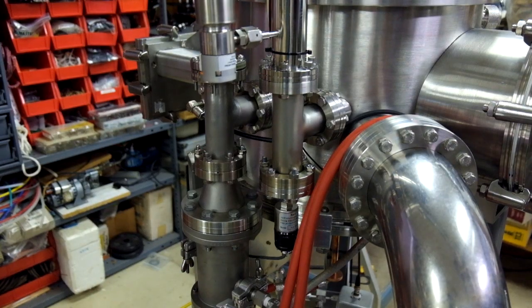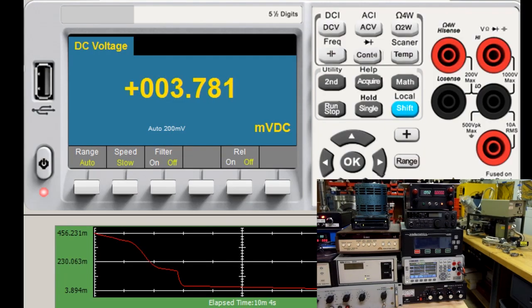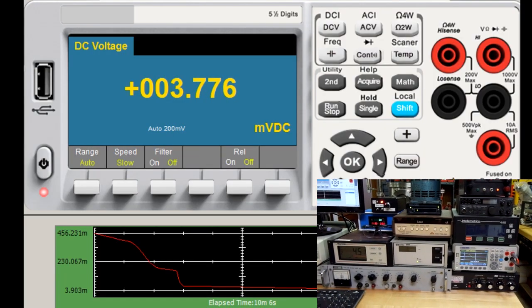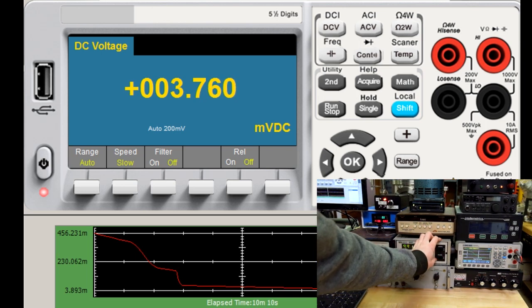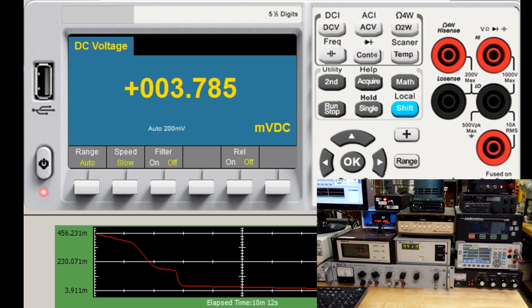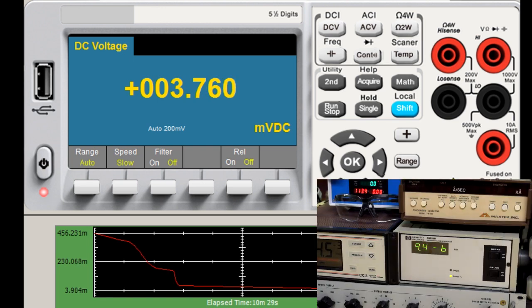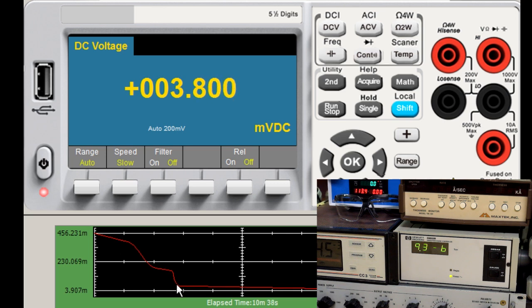So I'll pump down the chamber and then we can start experimenting with it. Please excuse the noise — I've got a mechanical pump and two turbos on right now, and we've been pumping for about five minutes. We're within the pressure range to start the RGA, which is great. You can see on screen the pumping curve: this portion here is the mechanical pump, then I turned one turbo on, then a second turbo pump, and now we're approaching base pressure.